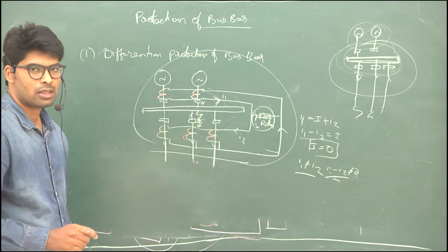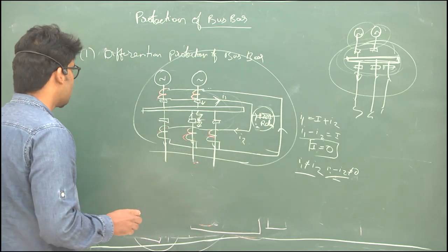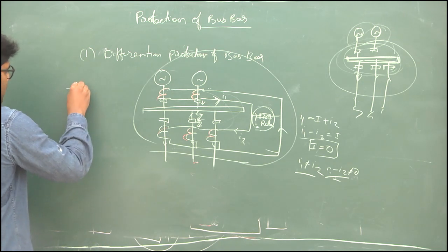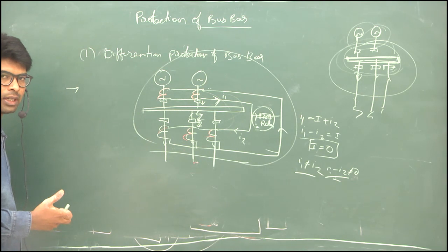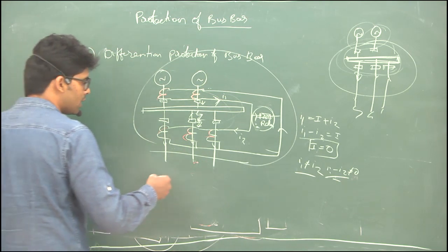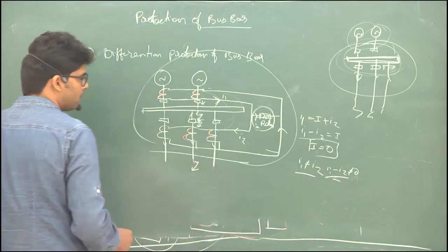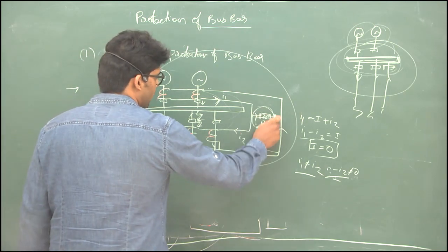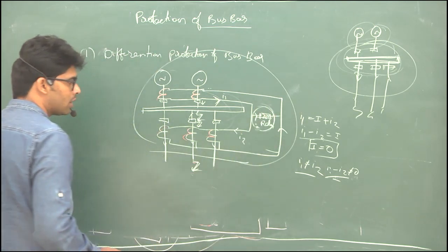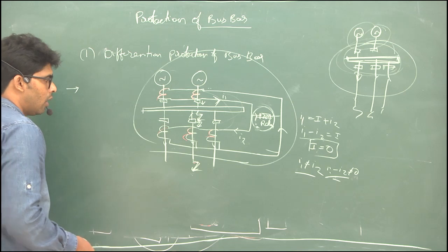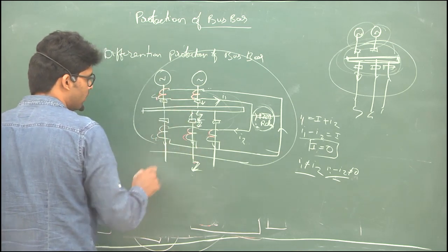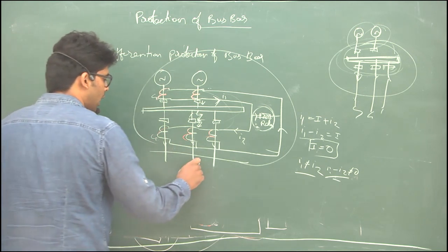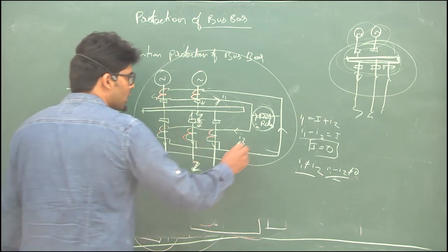But differential protection has a considerable disadvantage. Why? Because in differential protection the CTs can get saturated. That is the main disadvantage we have. If the CTs are saturated, the relay will operate for an external fault also, a malfunction. The CTs in differential protection have the same configuration, so even for an external fault the relay can operate.